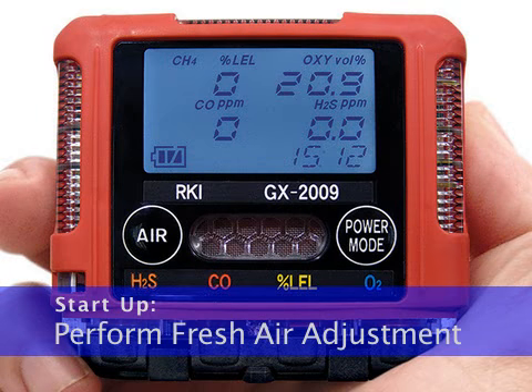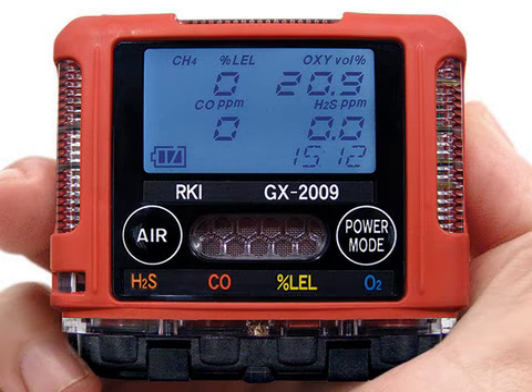Before using the GX-2009, you should perform a fresh air adjustment. Performing this adjustment ensures accurate gas readings as long as the calibration is current. Make sure you are in a fresh air environment which is free of toxic or combustible gases and is of normal oxygen content. Normal oxygen content is 20.9%.